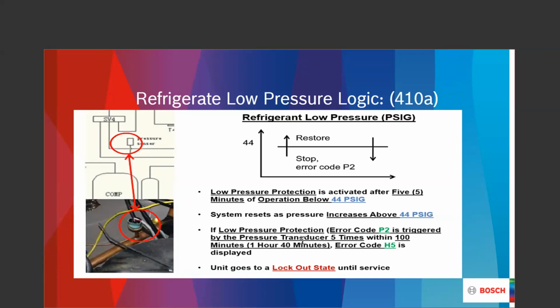We'll have to come out, pull the disconnect, basically seeing what's the problem with the low pressure. Low pressure is a restriction. Low pressure is a refrigerant circuit that has gone south on us, from a hole in the line or a bad brazing joint, things like that type scenario. So low pressure is the P2 or the H5 on the fault code.